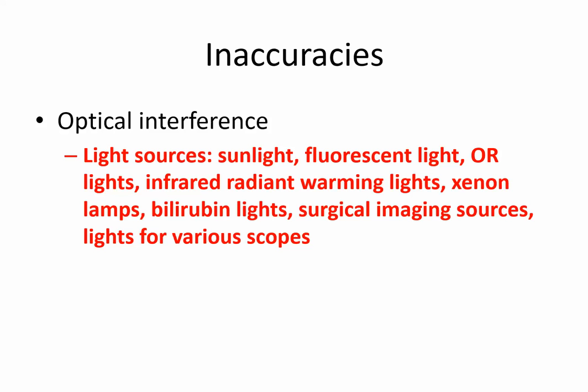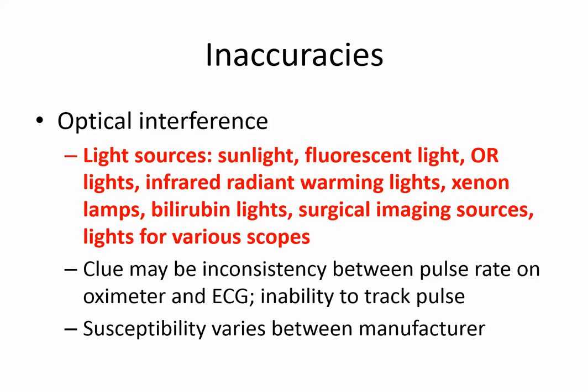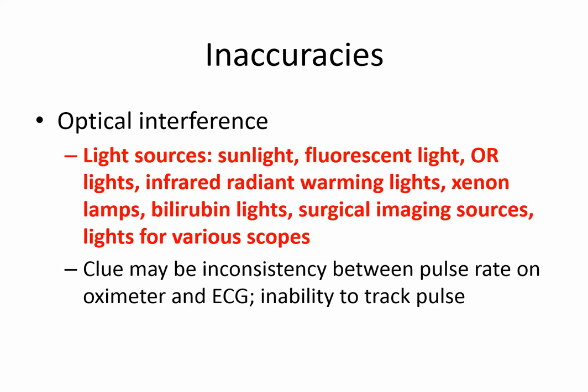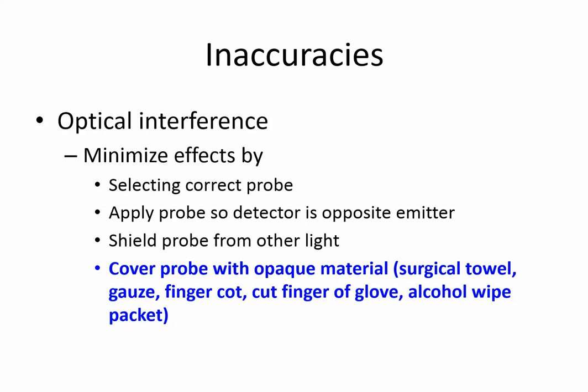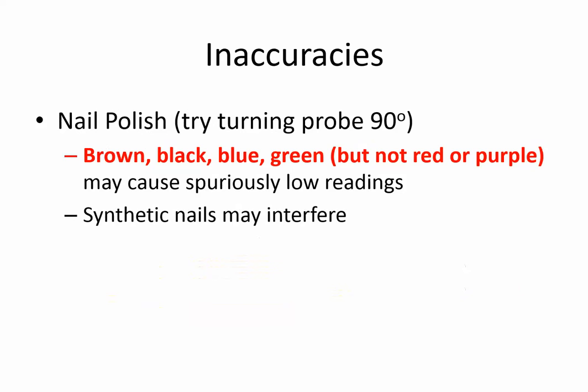Optical interference also can cause inaccuracy. You're aware of the problems with light sources from various different lights. One of the clues may be the inconsistency between the pulse rate on the oximeter and the EKG, or the inability of the pulse oximeter to track the pulse. The susceptibility varies between the manufacturers. You can minimize the effect by something as simple as putting a blue towel or an alcohol wipe packet over the finger in an attempt to shield the probe from ambient light.